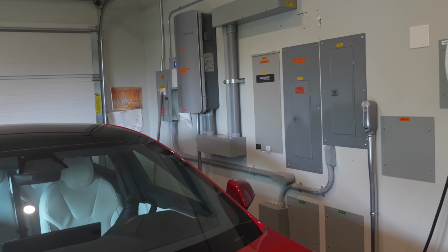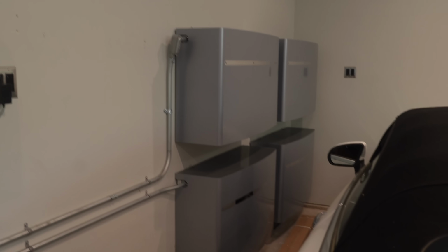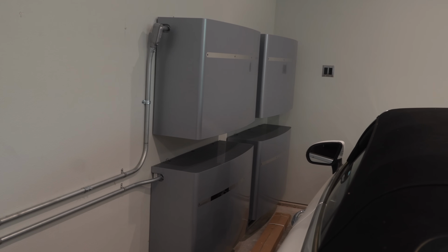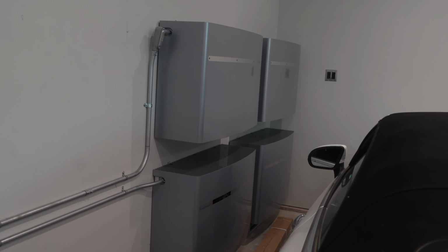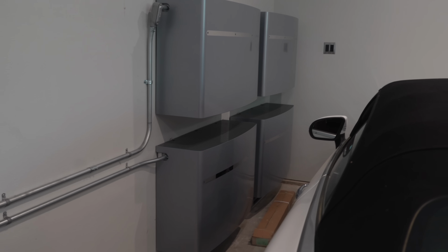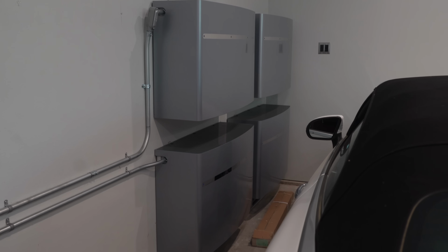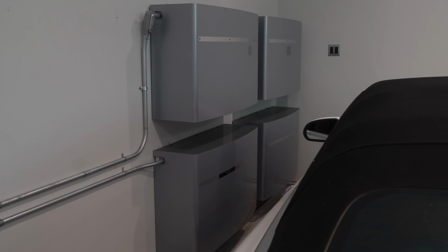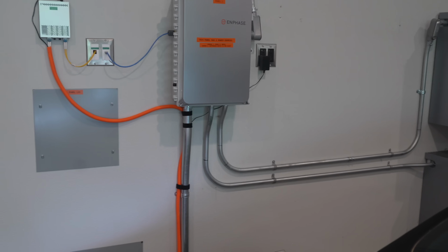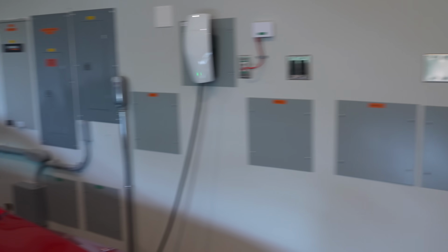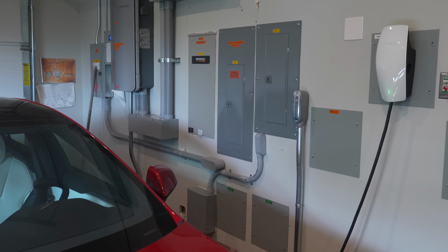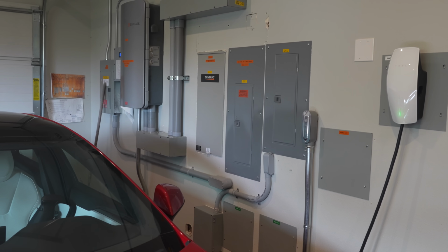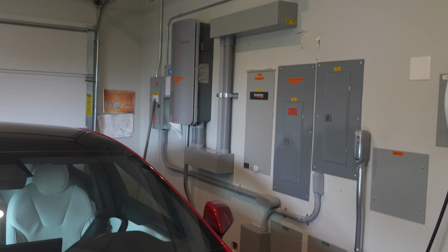And it relies on a couple of things. One is batteries, and so there are 4 of these 10.2 kilowatt hour lithium iron phosphate batteries. And these batteries are DC batteries, and then there are AC reverse microinverters inside of there that produce AC and go into a little grid combiner, and then eventually feed back into the main house grid. And of course there are 53 solar panels on the roof, and those all feed in as well.